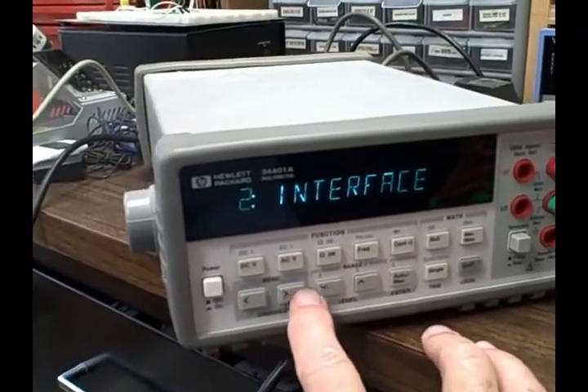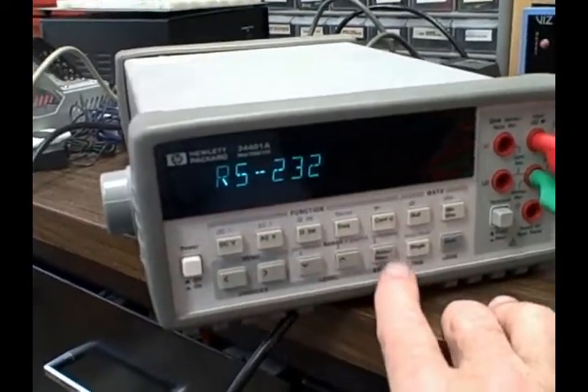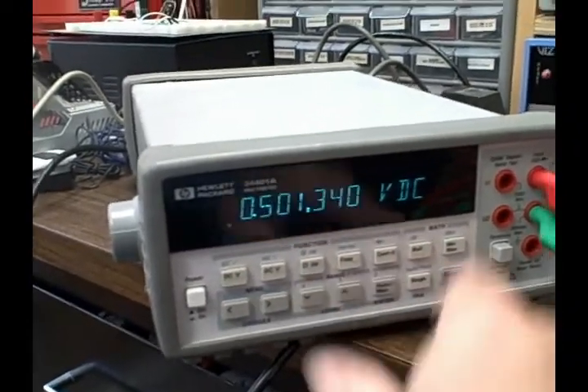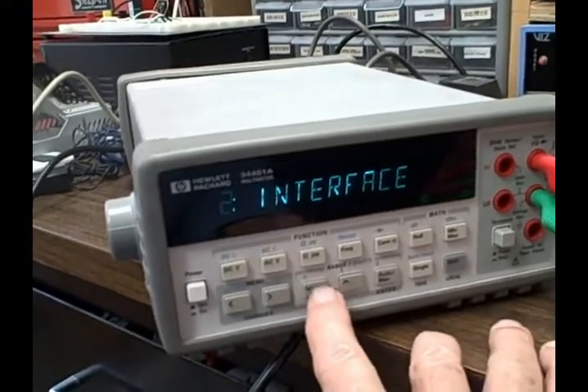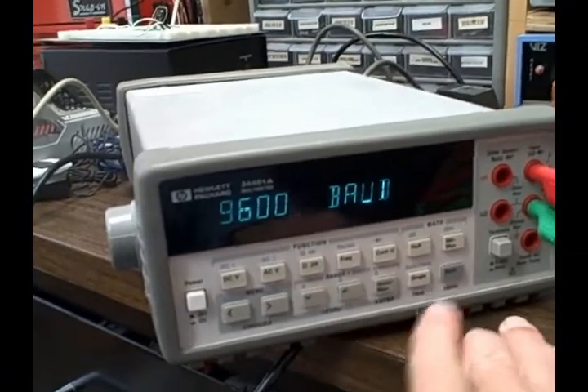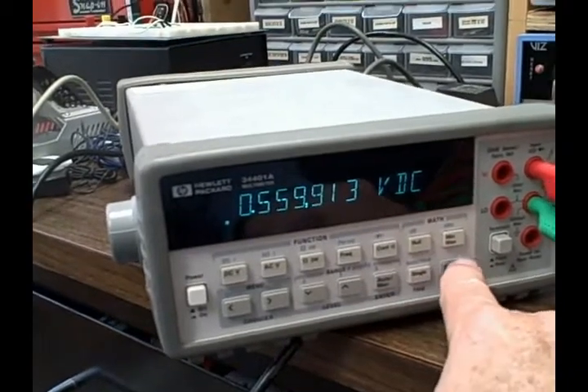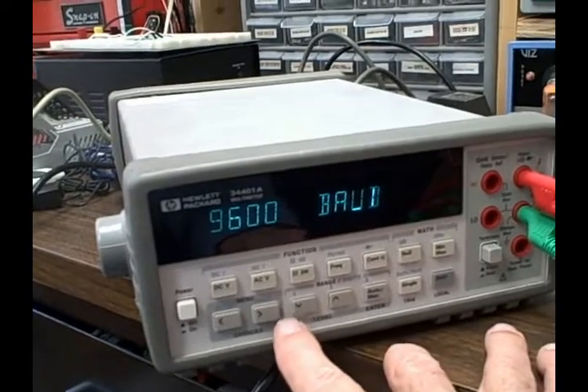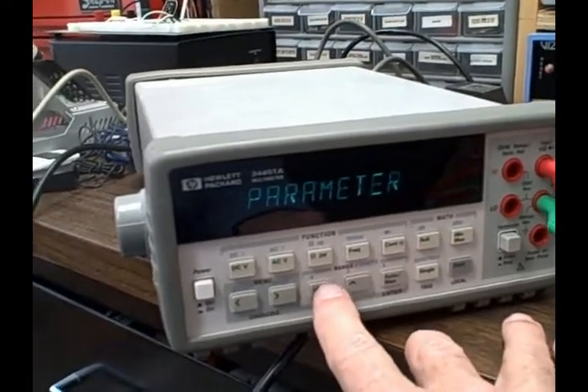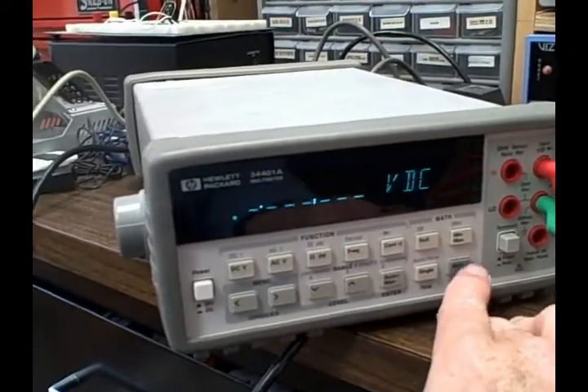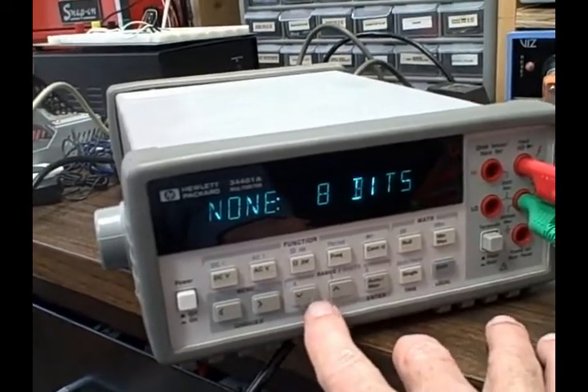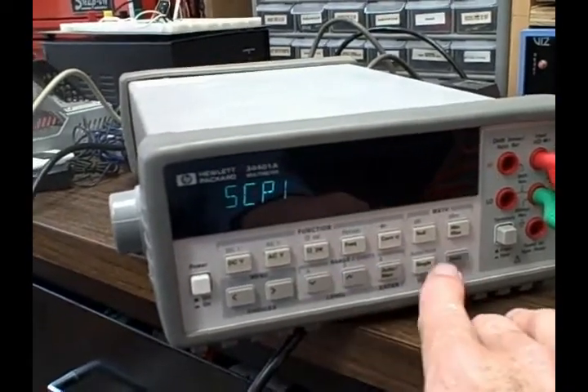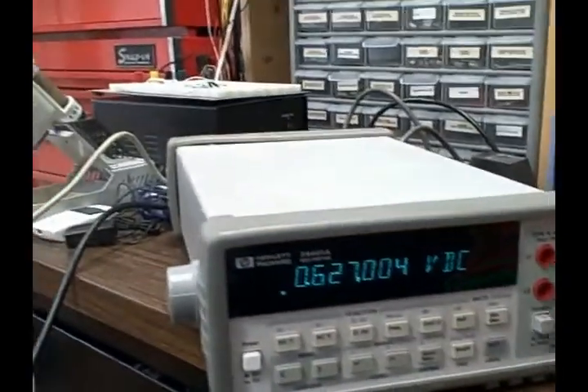So now baud rate I chose 9600 and I accepted it to kick me out. I'm going to go back in again. We're good there on the parity. I want none with 8 bits and I'm going to confirm that. And finally language. I want SCPI and I'm confirming that as well. So now I'm all set up. I should be able to communicate. I've connected up. I've got my null modem working. All I got to do over here now is bring up the software which I downloaded and placed on my computer.